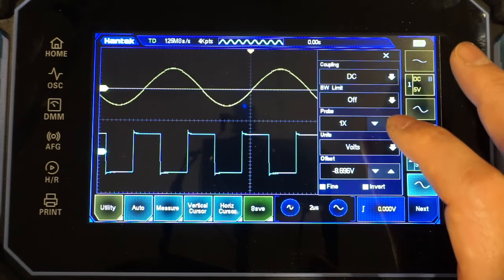And similarly, if I want to increase the vertical, I just do this here, and you can see that the vertical changes. Of course, you can always use the button on the side if you find it easier to reduce the verticals, and you can also use the button at the bottom to change your time base here.